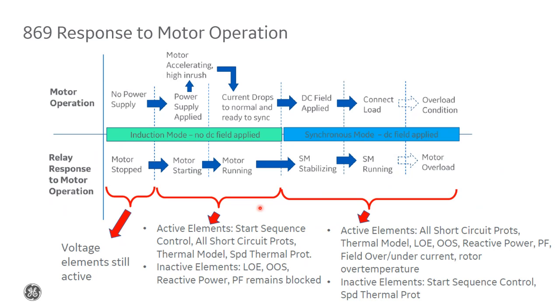Before we go into detail, I think it's important to note that there's different stages between the motor state of operation, which is at the top, what the relay registers, which is in the middle here, and exactly what protection elements are active and inactive during these states, shown at the bottom. So first, when the motor has no line supply feeding it, the breaker or contactor is open, the relay simply registers the motor is in stop state, and during that time, the only protection that's active are the voltage-related ones. Everything that has to do with current is non-operational during this motor stop state.